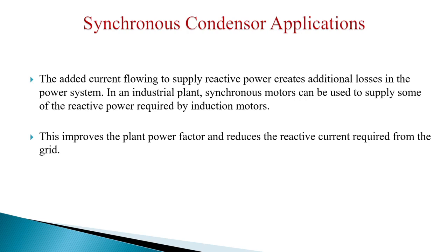In an industrial plant, synchronous motors can be used to supply some of the reactive power required by induction motors. So this will improve the plant power factor and reduce the reactive current required from the power grid.